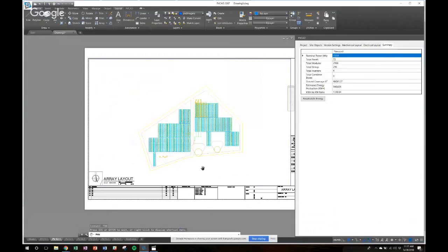And I think we have one other question. So if you've noticed, you're able to string multiple strings at once into an inverter. Oftentimes people will try to string multiple inverters in once into an AC panel. And as I mentioned, this is one part of the PVCAD that is still going to take a bit of time. Still a lot faster than rendering it yourself in regular AutoCAD, but you must string each inverter individually into an AC panel. So those are two smaller questions.